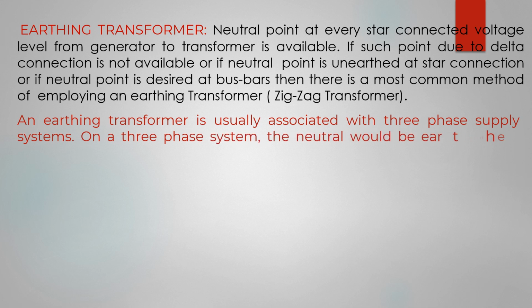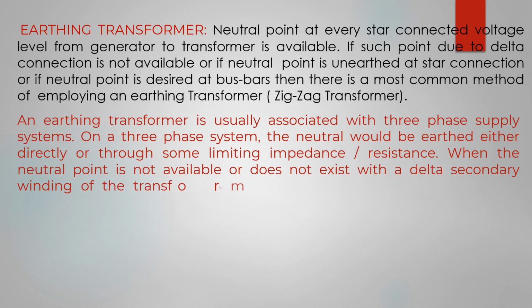An earthing transformer is usually associated with a three-phase supply system. On a three-phase system, the neutral would be earthed either directly or through some limiting impedance or resistance. When the neutral is not available or does not exist with a delta secondary winding of the transformer, a neutral point needs to be created. An earthing transformer consisting of a zigzag winding is used to create that neutral point.